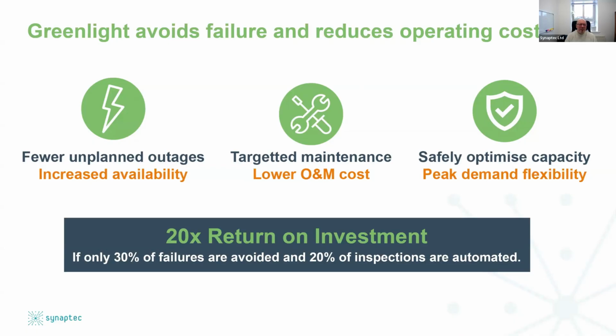And then over the lifetime of the array, remember, these sensors never need to be replaced, recalibrated, maintained, or updated, or have components changed out inside. They will operate that entire life untouched. Once you fit them, you forget them, they will operate. You've got this idea that across the entire operating life of a project, you're going to avoid several outage events. So the return is immediate. You get your payback if you save one fault, but if you save maybe even a third or even 40% of the potential failures that were expected in the risk analysis, you're likely to get something like a 20x return on investment here, because you're avoiding not all of the failures, but if you avoid a third of them, you'll make your money back, and you'll make a significant saving on optimized scheduled maintenance.